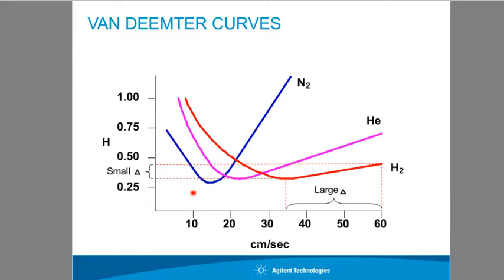So in choosing your carrier gas type, this illustrates that very well. With the cost of helium, a lot of people are actually focusing on nitrogen. It's a lot less expensive. It ironically is actually more efficient. As you can see, it's the lowest one here on the curve, but it is also at the slowest velocity.